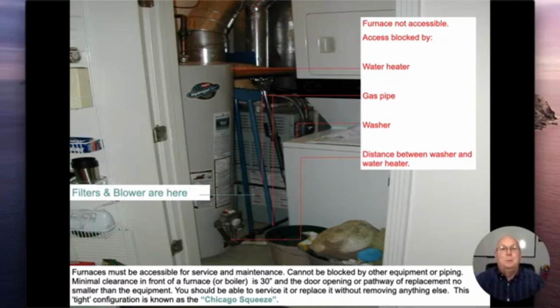All right, I would have to remove the washer-dryer combination, the water heater, all the gas piping, and everything else in there just to get to that furnace if I had to work on it. Not to mention, if that door is shut and I don't have any louvers on it, then the dryer's blowing air out. I'm going to be backdrafting my water heater, my furnace, if I don't have combustion air coming in there. It just has bad written in so many different areas.